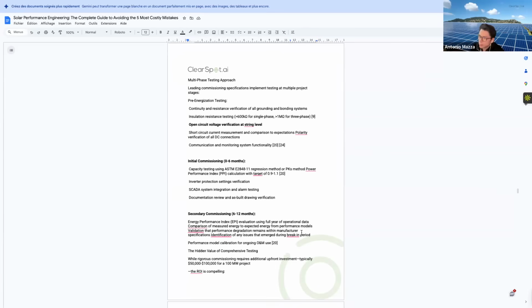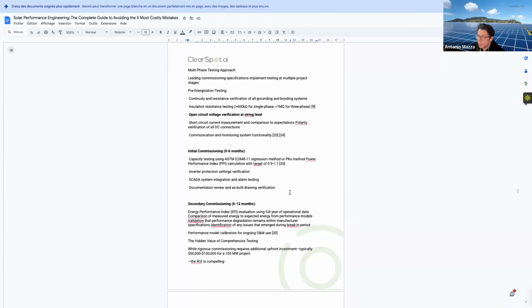Second commissioning, at 6 to 12 months: once we have an energy performance index evaluation using full-year operational data, we have more context, more information. We are more capable of pinpointing the performance model and validating what the degradation is, which should remain within manufacturer specification, and identifying any issues emerging during the break-in period.